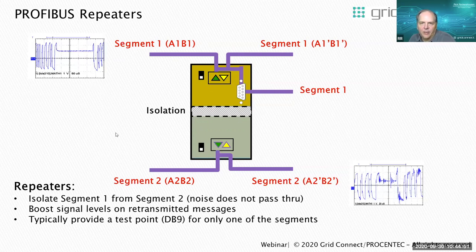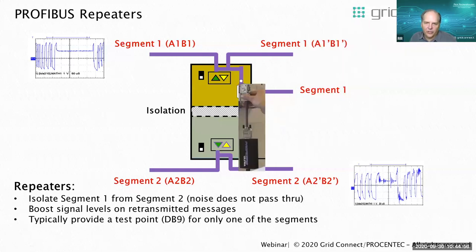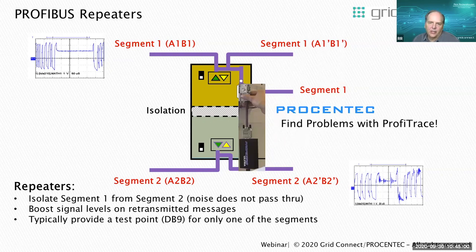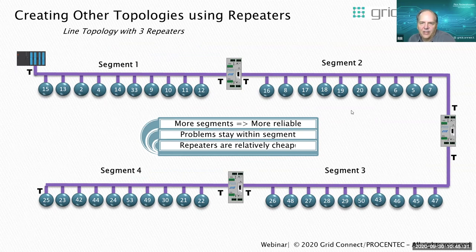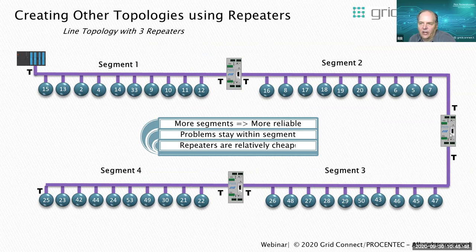If you do have trouble, you can connect your troubleshooting tool like Profitrace and check to see where the problem is — who has the reflections. In this case, looking at the top segment, if there's no problem up there, I would have to move my Profitrace to a connector on a device on segment 2 to see any noise, because the isolation does not allow me to see noise on the other segment. Following this example: if you add more segments, your networks become more reliable. Problems stay within the segments. A problem at address 7 won't show up on segment 3 or 4. Repeaters to add segmentation cost a couple hundred dollars and make a more reliable network.